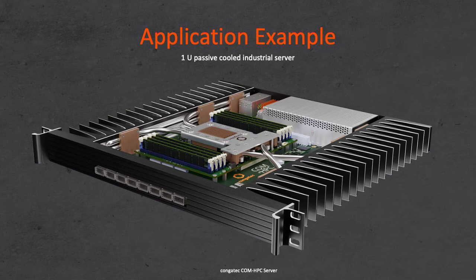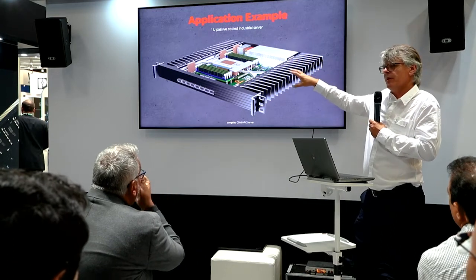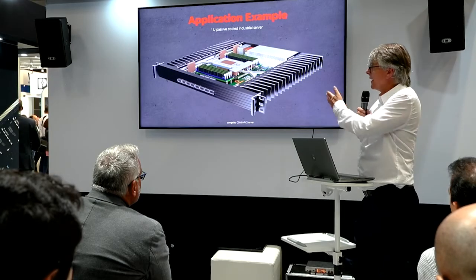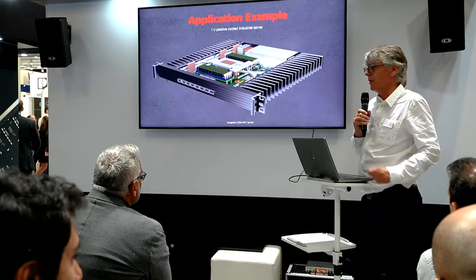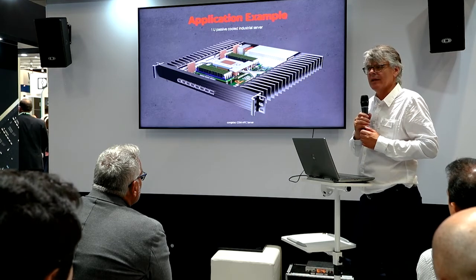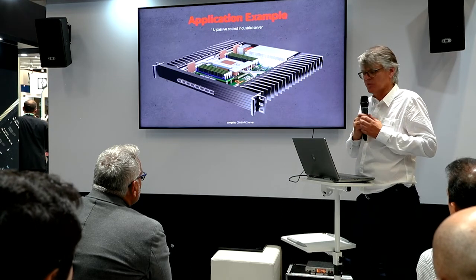Since these edge servers are on the low-power side, you can go for passive cooling solutions. You can see a typical cooling application here: on top of the CPU and DC-DC converters, we use what we call a heat pipe adapter. The silver components are the heat pipes, which transmit heat completely without fans to the outside of the chassis. This means we can create completely sealed chassis - important for edge servers - and achieve fully passive cooling. Fans are always an issue for long-term reliability, and even for extended temperature ranges, this approach is viable.